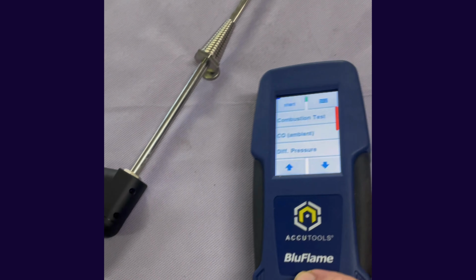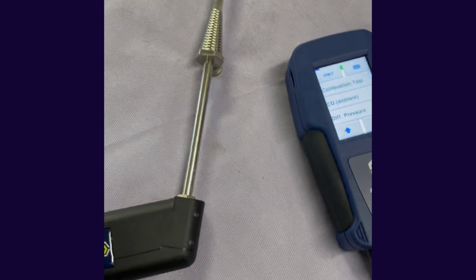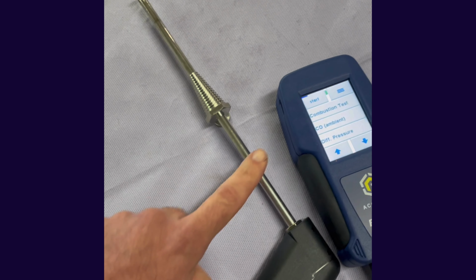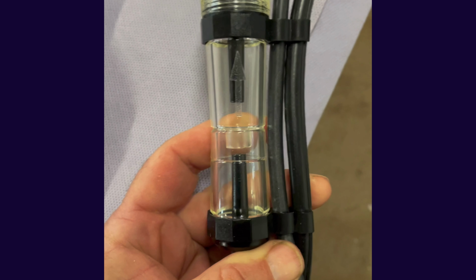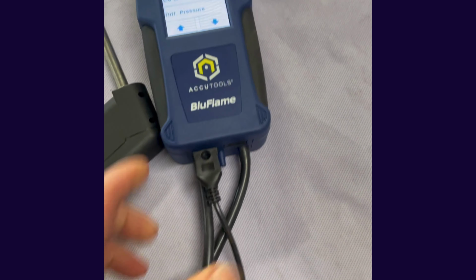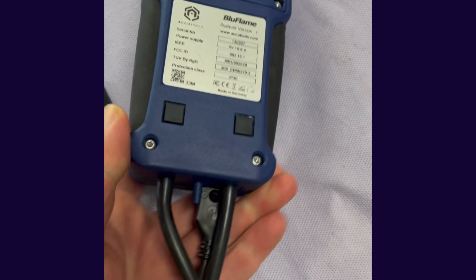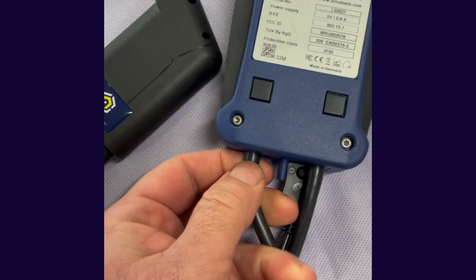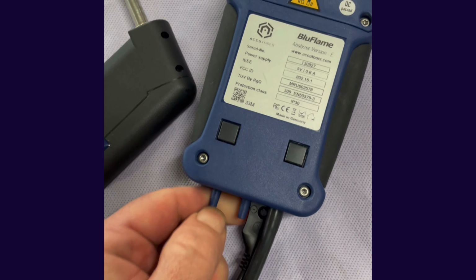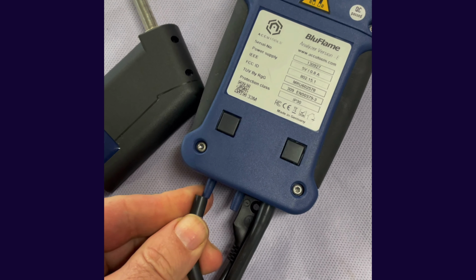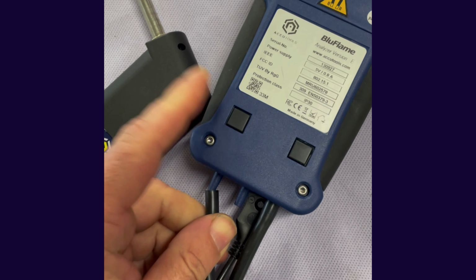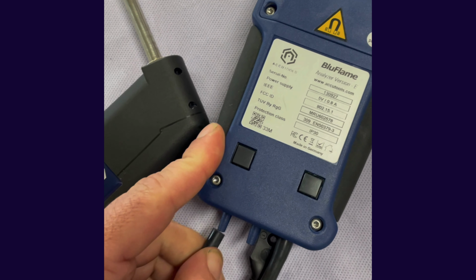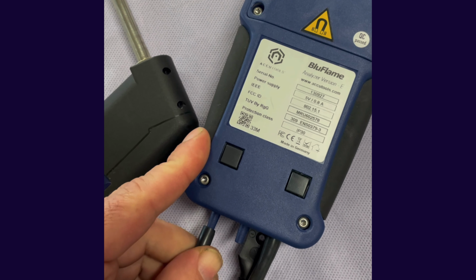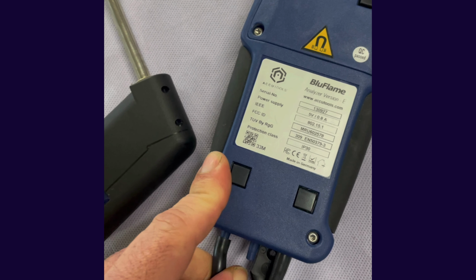In my career, I've used Bacharach and Testo. Right off the bat, the Accu Blue Flame is probably about half the size of the Testo 300. The probe and condensate trap all look pretty standard. I was initially concerned with the connection points on the hoses, but maybe the simpler is better. The thermocouple is standard and is a snug fit. I was attempting to do this with one hand.